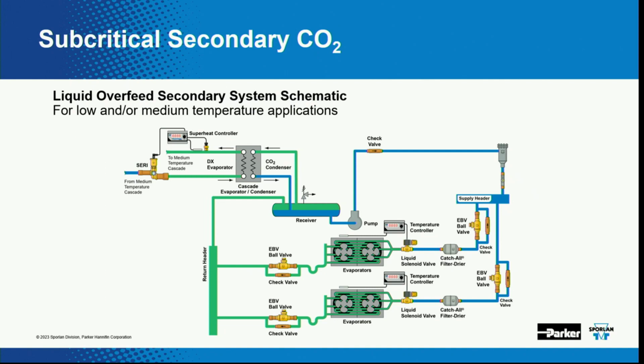Actually, the solenoid always stays on because if you shut off, it actually gets even colder - when it starts boiling off, it will make it colder. So now you really drop the temperature faster. As the CO2 return comes back, it's getting colder when you do that - it's just the opposite logic from normal refrigeration systems we use. Yeah, that's a good point.